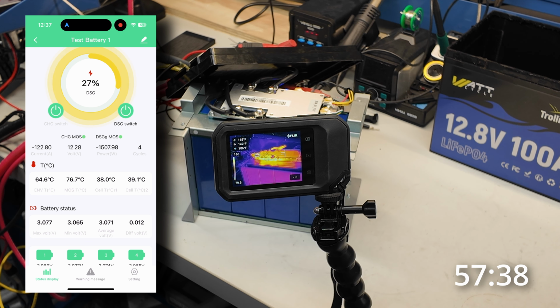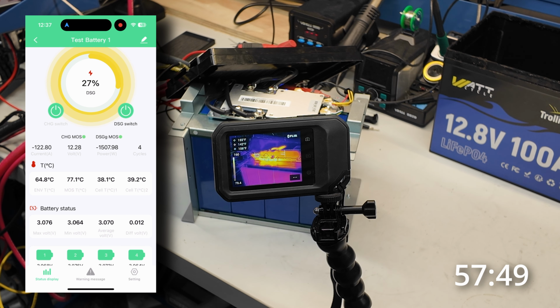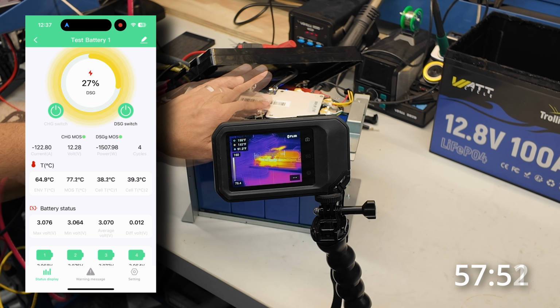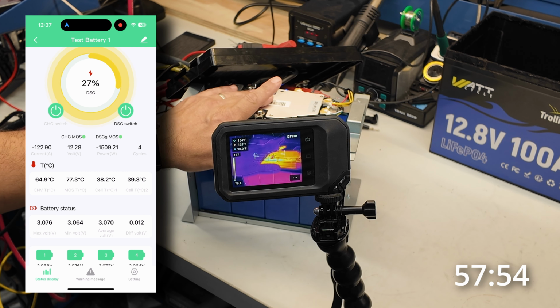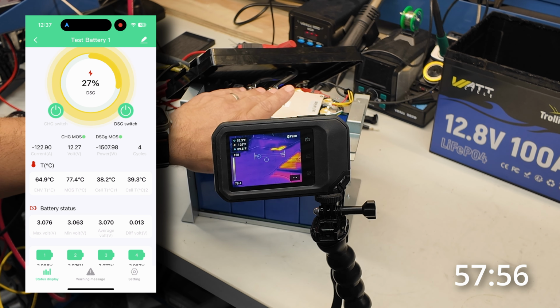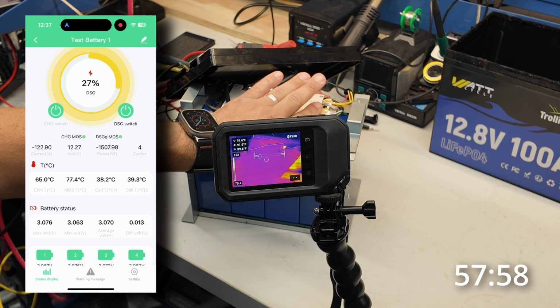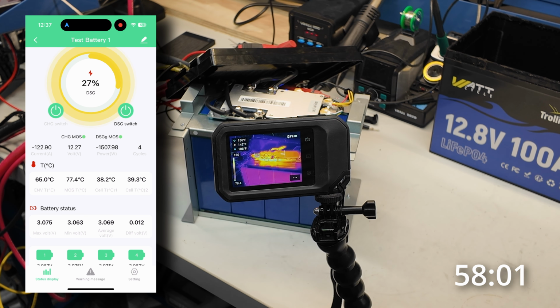In line with those hotter temperatures we were seeing, we are up to 76.6, 77 degrees Celsius, which is 170.6. Things are definitely warm in the battery. We're just getting to the point where it's not comfortable to keep your hand on the heatsink or the connections themselves. I'd say the entirety of the battery is pretty warm, and we're seeing that reflected with some 155 degree peak temps.